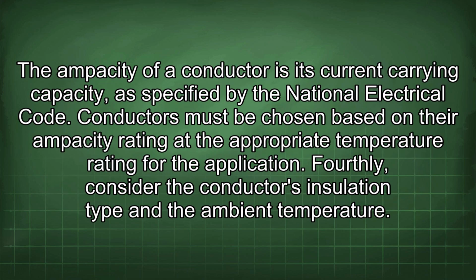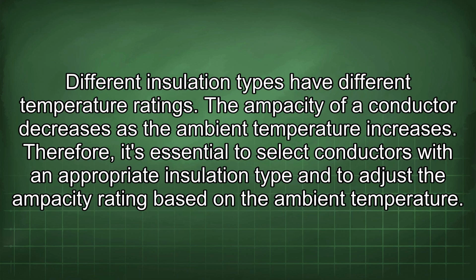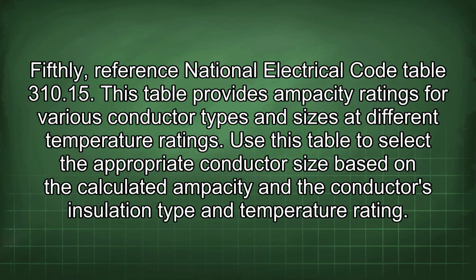The ampacity of a conductor is its current carrying capacity as specified by the National Electrical Code. Conductors must be chosen based on their ampacity rating at the appropriate temperature rating for the application. Fourthly, consider the conductor's insulation type and the ambient temperature. Different insulation types have different temperature ratings. The ampacity of a conductor decreases as the ambient temperature increases. Therefore, it's essential to select conductors with an appropriate insulation type and to adjust the ampacity rating based on the ambient temperature. Fifthly, reference National Electrical Code Table 310.15.